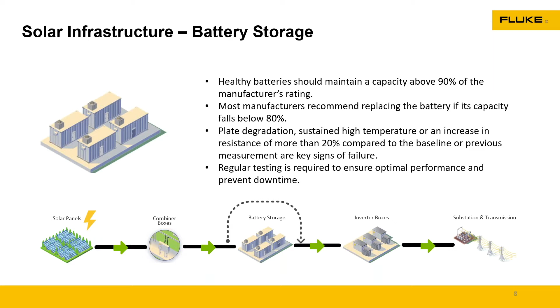But if you do have battery storage, they need to be tested. Most manufacturers recommend replacing the battery when it falls below 80% of its capacity. So we want to make sure we're able to test that type of stuff and get out there and troubleshoot it, to make sure that the battery storage systems are going to dump when they need to dump.